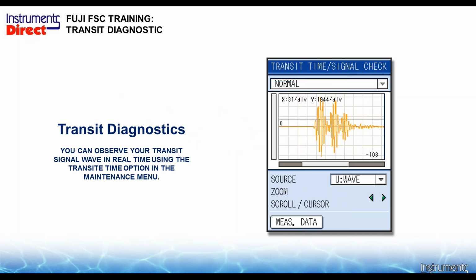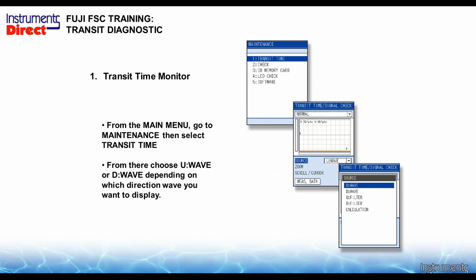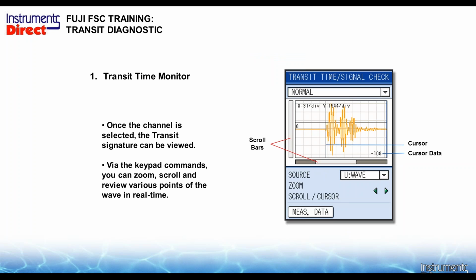If you needed to have some unique diagnostics, this is for the advanced user. Most of the time, you don't need this at all. If you have a difficult application where you're having some interesting side effects, you talk to support. They may ask to get some information here. To look at the diagnostic mode, from the main menu you would go to maintenance, then select transit time. And then here you can select the upstream wave or the downstream wave, and this would tell you whether we had a damaged transducer or a damaged cable, perhaps. So that's shooting for trouble, to look for trouble.